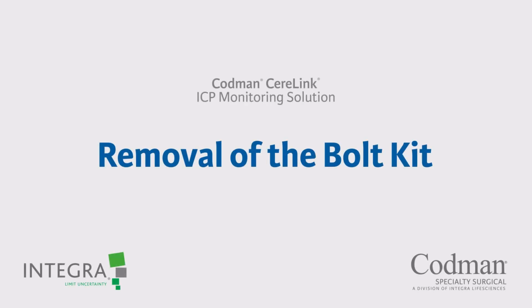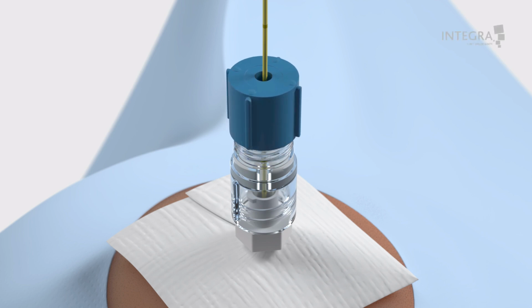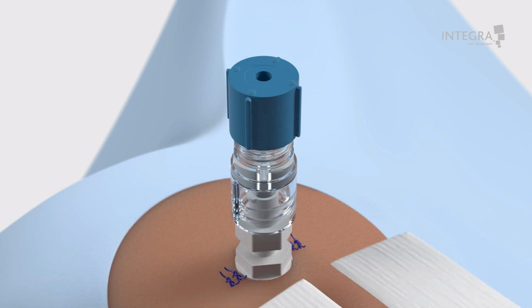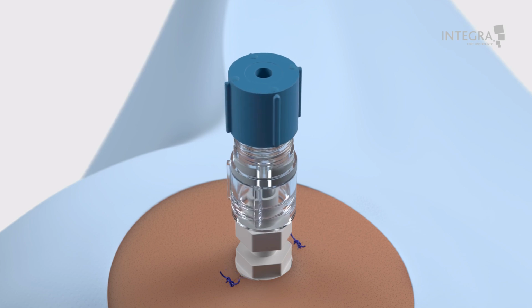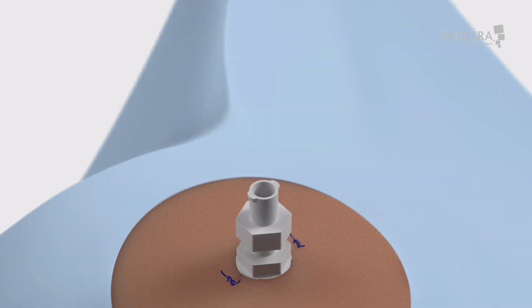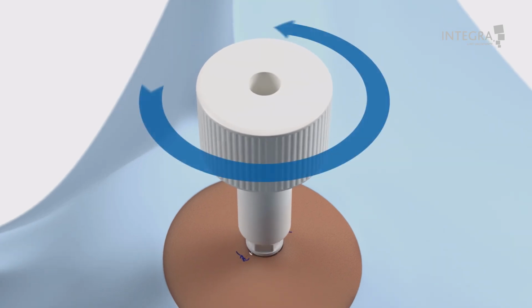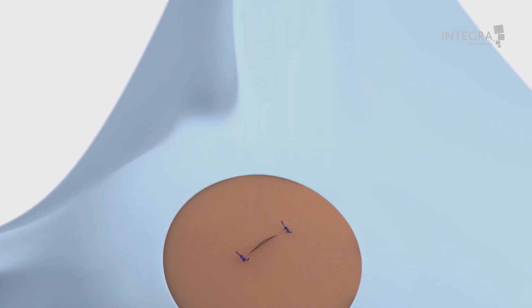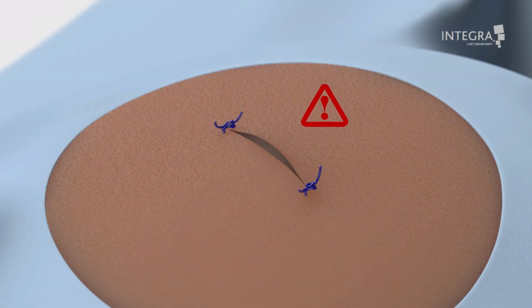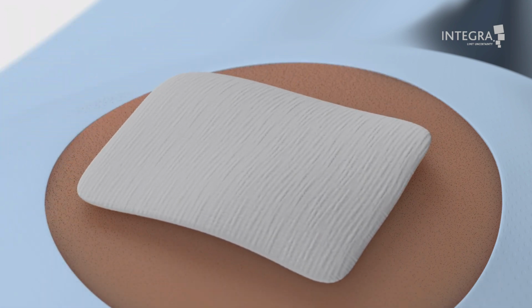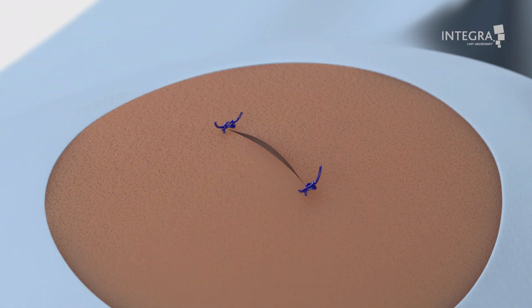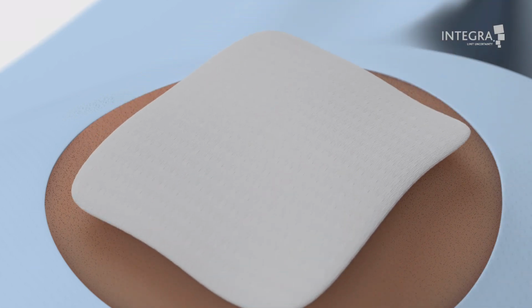4. Removal of the bolt kit. Carefully withdraw the ICP sensor from the bolt assembly. Check that the sensor is complete on removal. Remove the dressing around the bolt and 1 or 2 sutures closest to the bolt. Using the sterile screw handle provided, turn the screw counterclockwise until free. Caution: make certain that all the washers have been removed from the incision area before closing. Apply pressure with sterile gauze until hemostasis is achieved. Close the incision again in one layer with uninterrupted sutures. Apply a dry, sterile dressing.